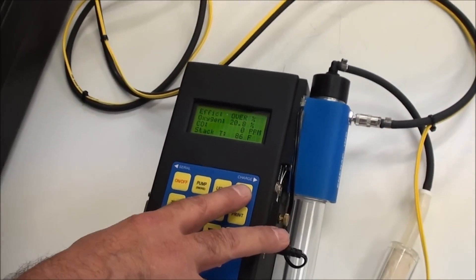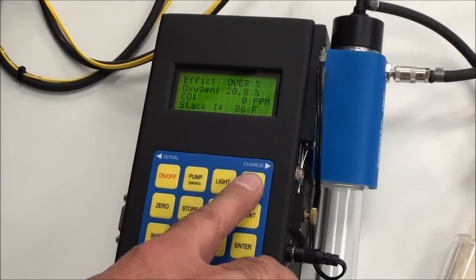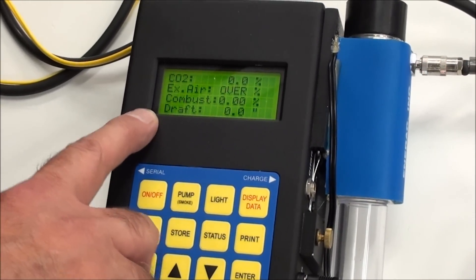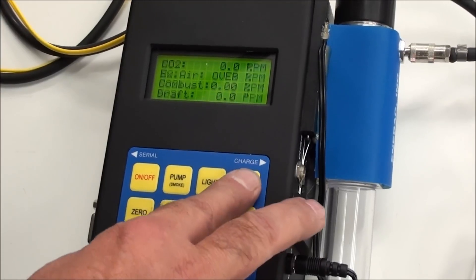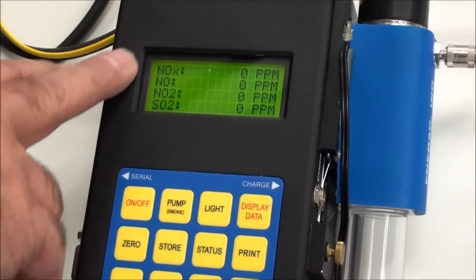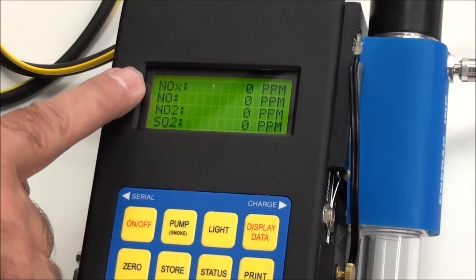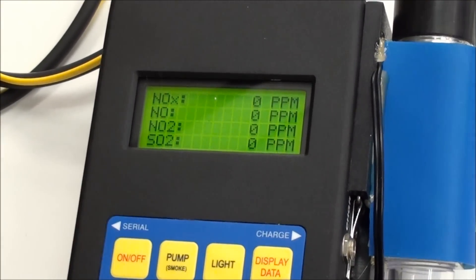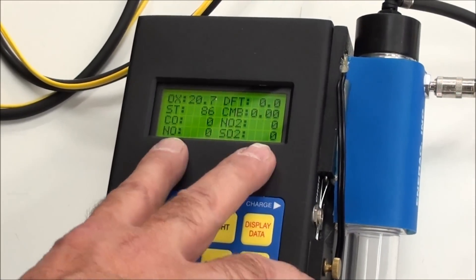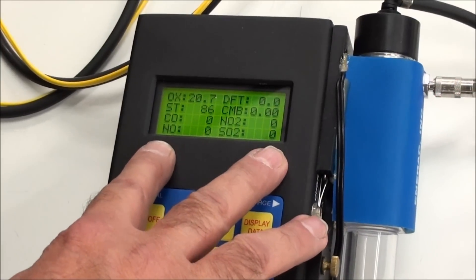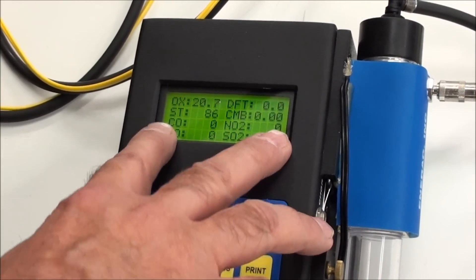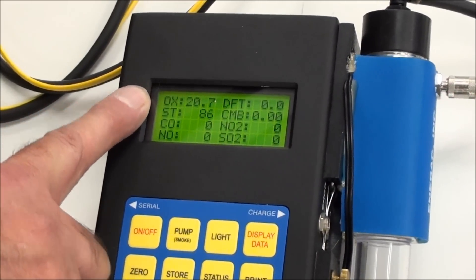Now what you'll do is you can check by simply hitting the display data button, and you toggle it through. You'll see on the second screen, you've got your CO2 excess air, combustibles, and draft. Next screen, these are your toxic sensors. The NOx is a total of the NO plus the NO2, and then you have the SO2. And the last screen is just a compilation. It gives you all the readings on one screen that you might be interested in. Shows you your toxics, your stack temp, your combustibles, your draft, and your oxygen reading. And then you hit it again. It goes back to the beginning.